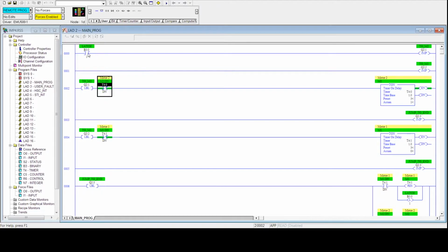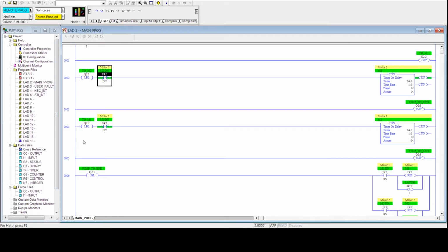Okay, so let's follow this one. This latch command will not be on when the program starts, so it's going to skip this line, right? It will then go to this line, and this line is always true. And this line says to jump to the label that is motor 1, called To-Motor-1. So this jump command is going to skip this line of code and this line of code and go straight to here.